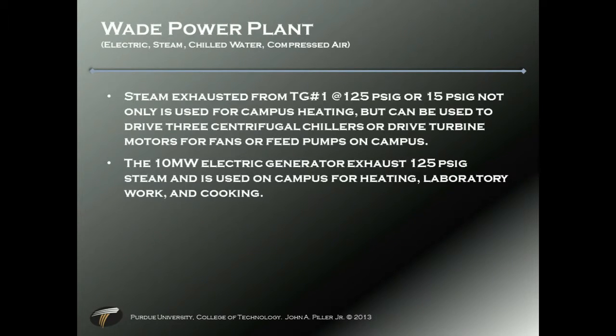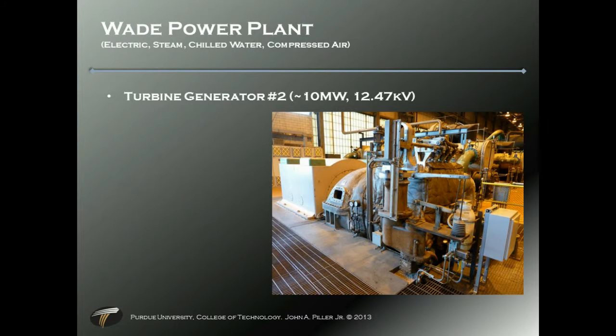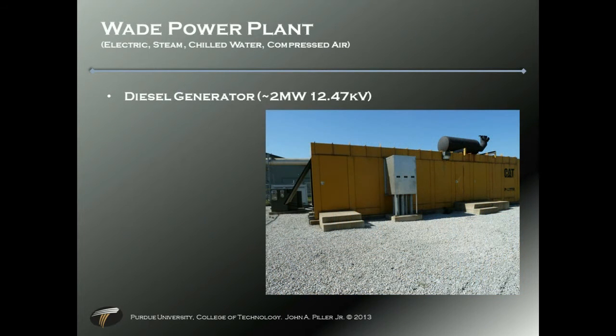Since we don't have the capacity to produce all the electricity needed on campus, we have to buy power from Duke. Duke is the local electrical supplier, like in South Bend would be AEP. Duke is the local there in West Lafayette. They have two substations, separate lines at each so that they can buy power from. They have a substation north, substation south. South has 2 lines coming in, north has 3 lines coming in, so Duke would select which line we are drawing power off.